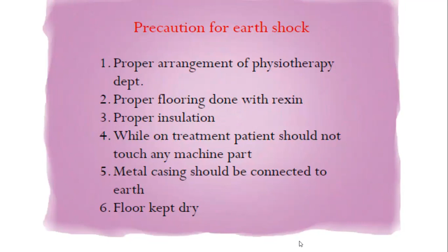Precautions against earth shock include proper arrangement in the physiotherapy department. Proper flooring should be done with Rexin, and proper insulation should be in place. During treatment, patients should not touch any machine part. Metal casing should be connected to earth, and the floor should always be kept dry.